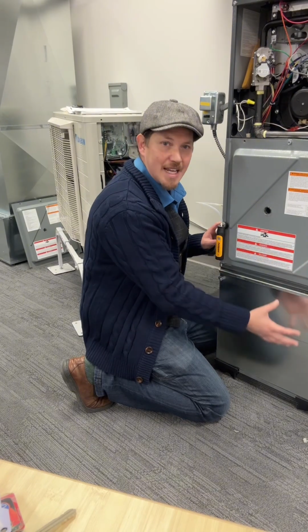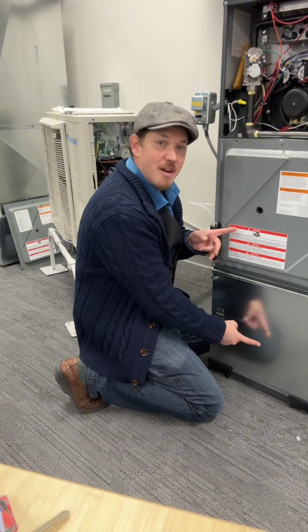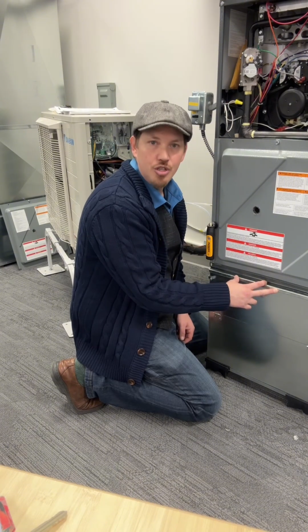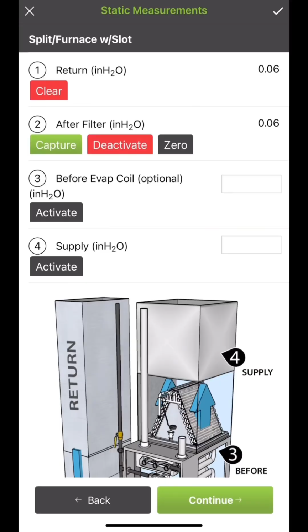So now I'm seeing how much stress on my blower motor am I getting from my return ductwork and from my filter. The difference between these two is what's called my filter drop. So with my filter drop, I get to see how restrictive this filter is. If you want to prove to a homeowner that a MERV 13 filter is not a good idea, you can check the filter drop. All right, now as we see here, as we switch our probe from one spot to the other, now we're reading that 0.32 after the filter and before the blower. So that 0.32 minus 0.06, that might be a little bit more than we wanted.